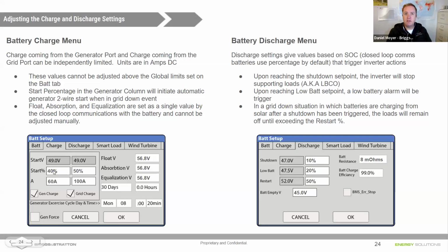Another thing you might notice here is the generator exercise function. Briggs and Stratton generators can automatically exercise themselves and also do the burn off cycle. You can disable the generator exercise in the Sol-Ark by simply adjusting that time to 0. If you put all zeros in the time for the hours and the minutes here, then that will disable the 2-wire signal to start from occurring. You can also force the generator to start up by checking the Gen Force box and clicking OK. You can turn it off by unchecking and clicking OK again.